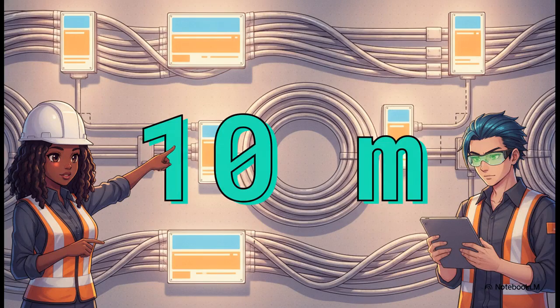But wait, there is a catch. If you choose to use that exception and not bond the metal tray because all your cables are armored, you must install permanent legible warning notices. These signs have to clearly read interlocking metal armor cables or continuous metal sheath cables only. And you've got to place these warning notices at a maximum spacing of 10 meters.